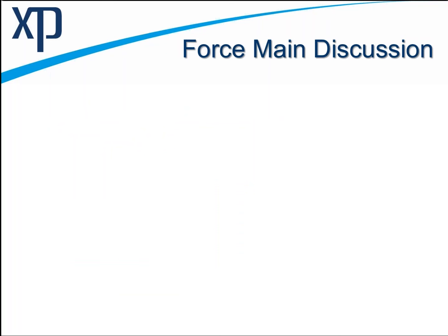So then we have force mains, and this has been a comment before too. Do I have to have a force main? No, you don't. You can have a lift station, especially a very deep lift station, potentially lifting, let's say, 30 or 40 or 50 feet up and then discharging to a gravity line. The pump discharges directly to gravity or through a very small section into gravity. However, if you have a pressurized system, that's called a force main. Simplified first, as I say here, is to defeat gravity, right, from one cost or another. It makes more sense to pump this thing and not be impacted by physical limitations than it would be to treat it, let's say. And so you're going to have this force main.